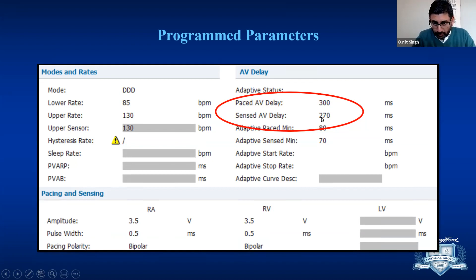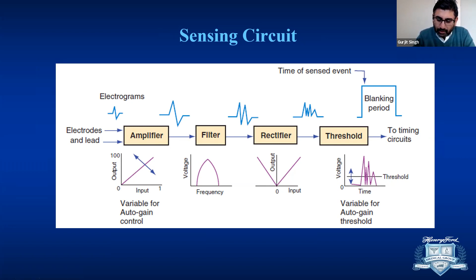It has to be amplified, it has to be filtered, then rectified, and then it has to meet certain threshold criteria before the pacemaker makes any decision. Doing so takes time, and usually that time could be anywhere from 20 to 30 milliseconds. So if your paced AV delay is programmed pretty close to your native AV conduction, you can see this kind of ECG where what we call this as a functional non-capture.